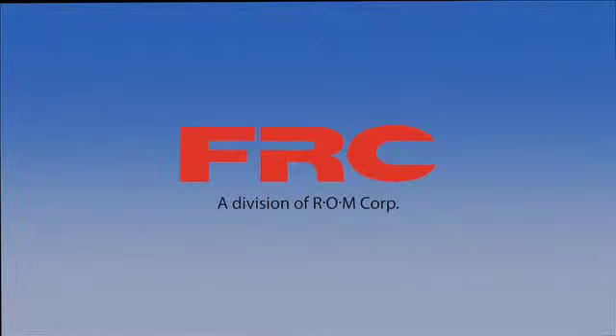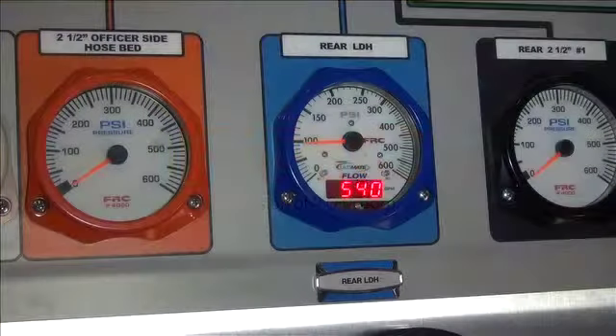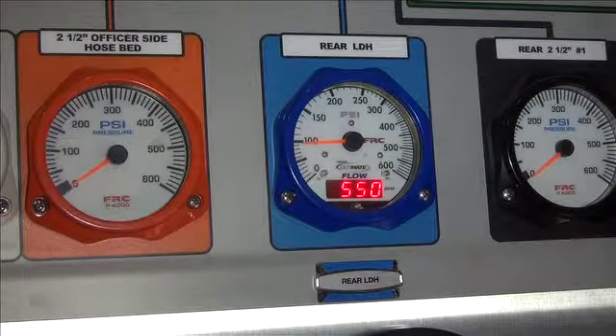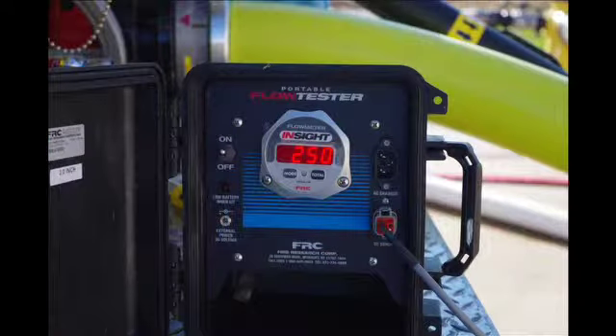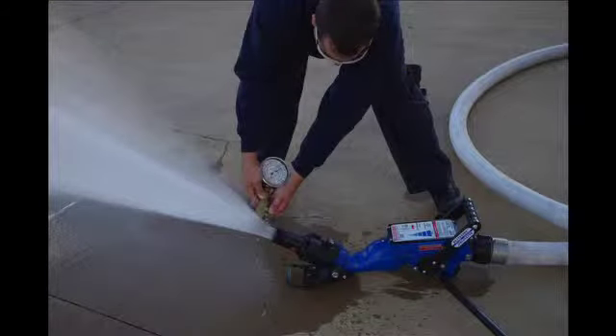Welcome to Fire Research Corporation's instructional overview on a multi-point calibration of the Insight ultimate flow and pressure meter. In order to calibrate a flow meter, you must use another calibrated flow meter or a pitot gauge and flow chart to get a steady reference flow.